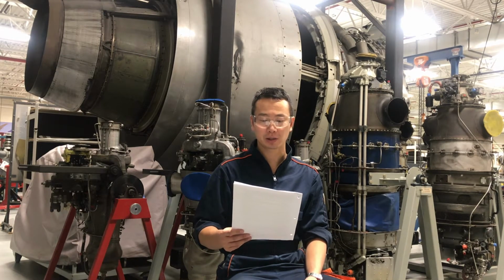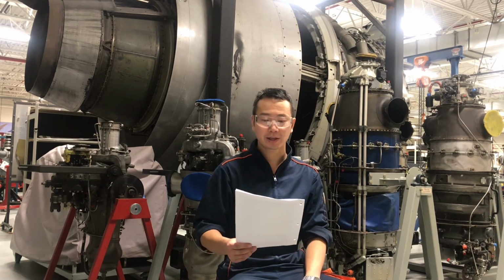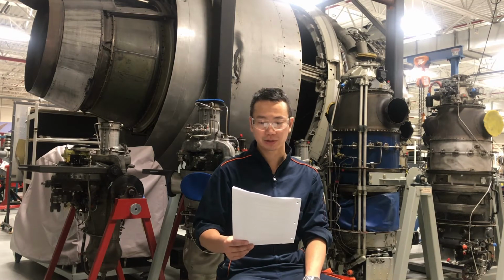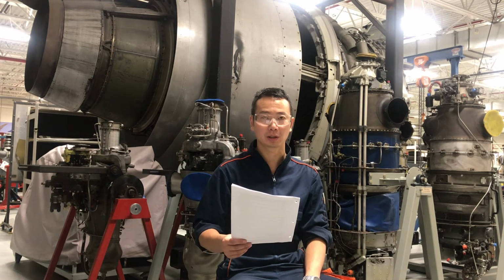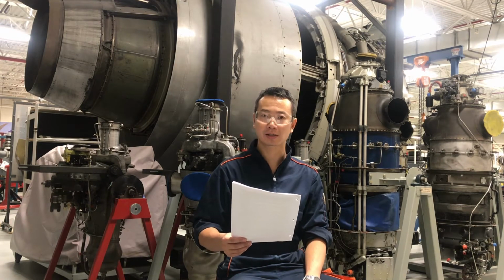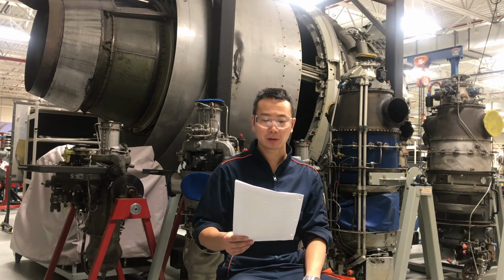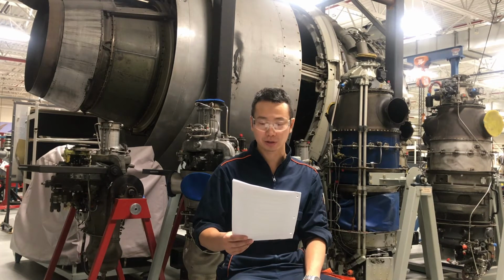And there are 2 types of tachometer. The first one senses the fan speed or the low pressure compressor speed, measuring the frequency of magnetic field interruption by fan blades, measured by an electronic circuit and transmitted to the gauge. Another kind of tachometer is the gear-driven shaft, where induced voltage and frequency are measured by an electronic circuit. It can also be called the tachometer generator. It works like a generator.